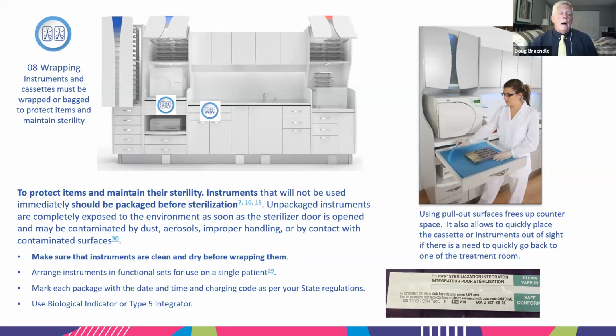Yeah, sure. Let me clarify also on that last point, use a biological indicator or type 5 integrator. Unfortunately, we don't have the "or" as an option. You are always going to be required, even in the states that don't adopt CDC guidelines, to do a biological indicator. If they go by the CDC guidelines, it's once a week. Once a week for every sterilizer that you have, you're going to have to run a BI.